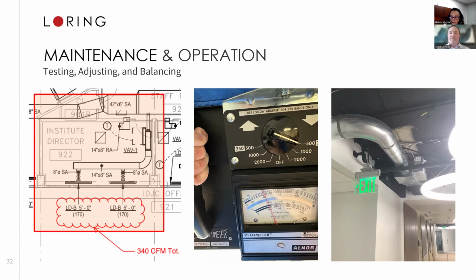And the reason is, in the picture on the far right, you can see the VAV serving the space. There's an inlet sensor on those VAVs that reports that CFM value back out to the BAS. Having not done a proper balancing process during construction, we were able to identify that they're getting temperature complaints because their airflow was deficient, even though the BAS was not flashing any alarms. They needed to calibrate that box properly in order to get usable, good data out of the BAS.